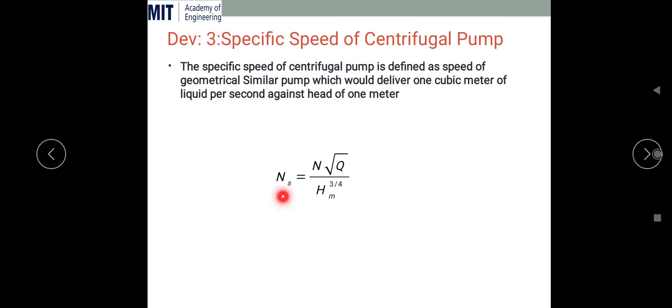The specific speed in a centrifugal pump is the speed of a geometrically similar pump which would deliver 1 cubic meter of liquid per second under a head of 1 meter — that is, 1 m³/s against 1 meter of manometrical head. The specific speed is given by Ns = N√Q / HM^(3/4), where N is the RPM, Q is the discharge in m³/s, and HM is the manometrical head in meters.